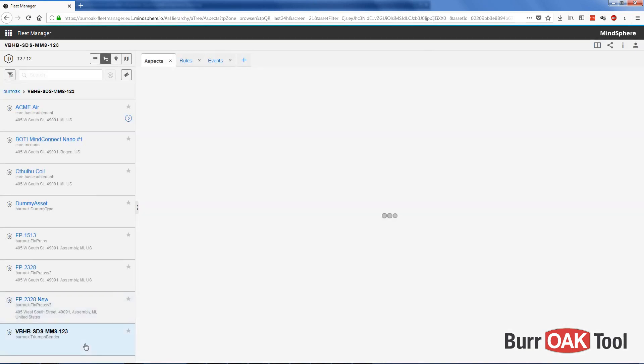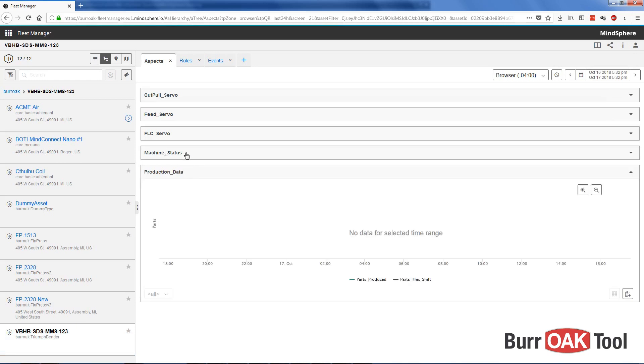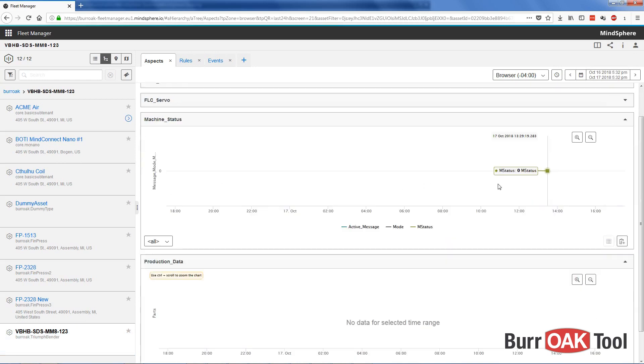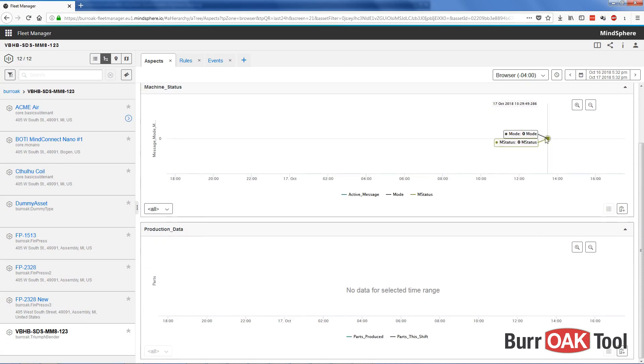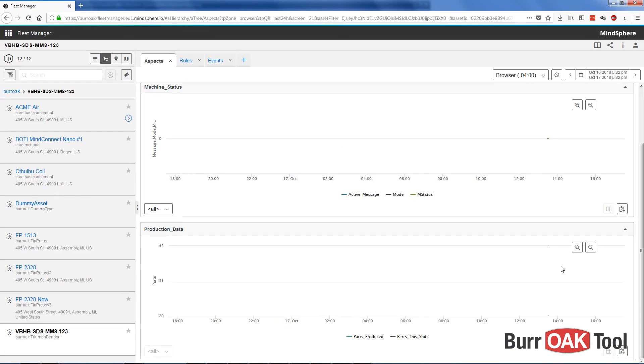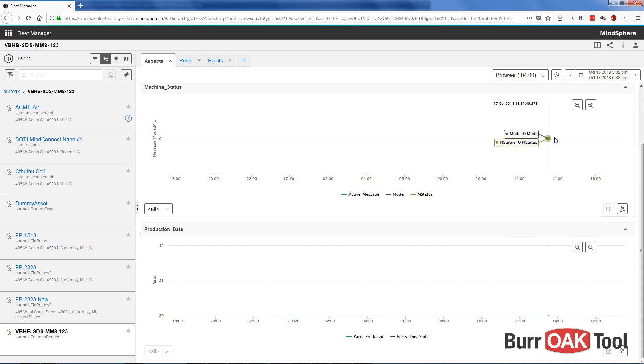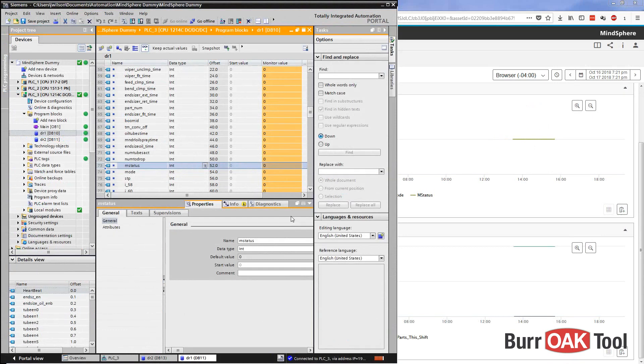Alright. Here's our VBHB asset. Here are our newly added aspects. I'll open both of those up. Now, oh! Looks like we've got a data point already. You'll notice there's nothing down here yet. It may take up to two minutes for data to start appearing. So I'm going to let this just sit here for a minute and we'll see if anything appears in our production data aspect. Oh! And there it is. We've got a data point. Parts produced, 42. Parts this shift, 20. That's perfect. I had gone online with the PLC on my desk and modified these variables so that we could make sure that it's working. So we see that both of those variables are working correctly. And both of these are currently reading zero. Now, I think that they are not both set to zero in the PLC, so we might need to do some troubleshooting there.